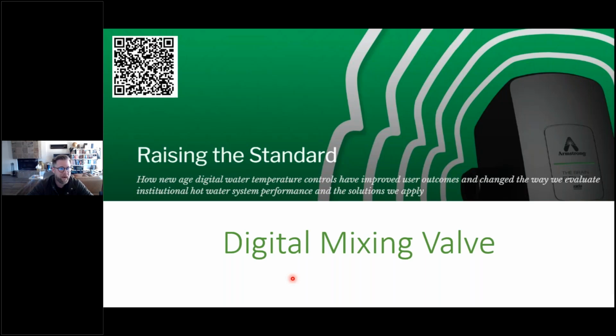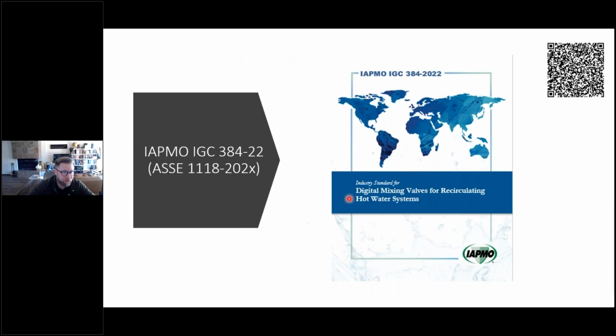Some other things that are coming up on the practical side is digital mixing valves. There was an article, there's a QR code that was put into Working Pressure magazine, which is the magazine of ASSE International. Would recommend getting a free subscription to that. It's a really great publication, lots of good articles in there. And this article put out the need for a new product standard that goes above and beyond what ASSE 1017 does, which is for master mixing valves. This led to the formation of IAPMO IGC 384, which is in process of hopefully becoming ASSE 1118 and an ANSI standard for digital mixing valves for recirculating hot water systems. And there's the QR code. I'm happy to report that all IAPMO IGCs are for free viewing, and actually all IAPMO and ASSE codes and standards have a free online viewer on our webpage, and so that one should take you to that webpage.